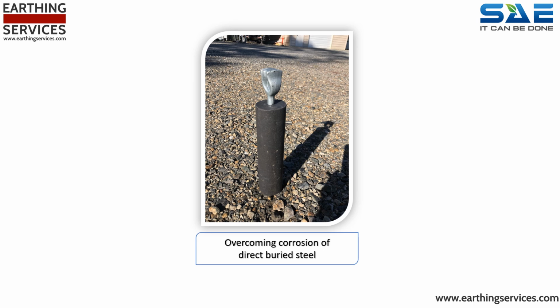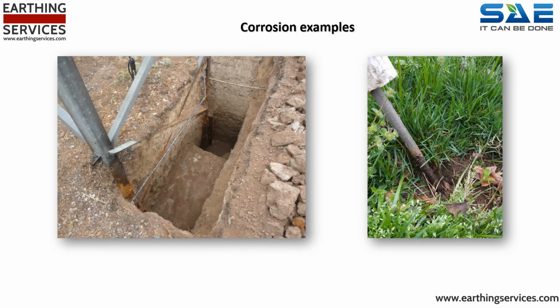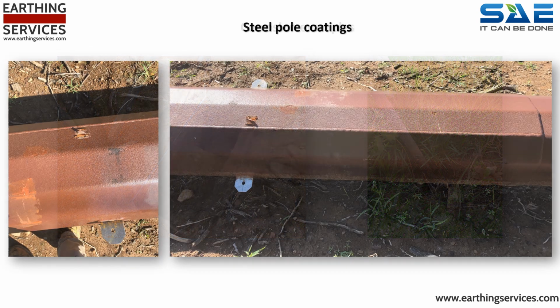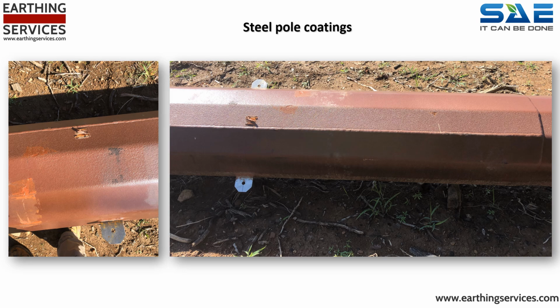We will now consider overcoming corrosion of direct buried steel in power transmission using Concrete. Here we see the corrosion of steel that has been buried. The traditional method of preventing corrosion on power transmitting direct buried steel is the application of insulating coatings. As the photographs demonstrate, these coatings are easily damaged when installing, and scratch points result in concentrated corrosion that then rapidly spreads.